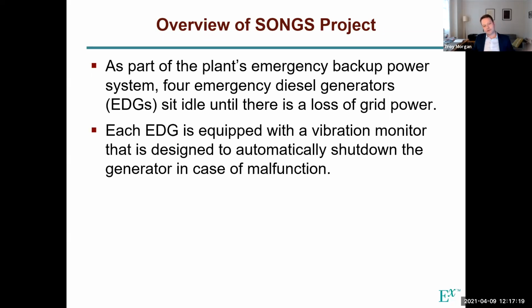Now, each of these generators is equipped with a transducer that's mounted to the top. And that transducer is meant to measure vertical vibration. The transducer is there to trip off the generator in case there's excessive vibration. And the excessive vibration is meant to indicate that the diesel generator may be malfunctioning. So some kind of eccentric loading, maybe there's a loss of a blade or something else that renders the diesel generator inoperable, and it gets tripped off before it damages itself or other things around it. So that vibration monitor is very much a part of the story.